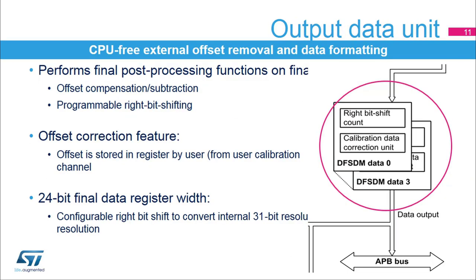The correct configuration must ensure the final data length fits into the 31-bit width, which is the resolution of the internal integrator. The width of the data coming from the digital filter must also be taken into account. The output data unit adjusts the final data before they are written to the final data register. An offset value that will be automatically subtracted from the data result for each channel can be defined in the offset register, determined using a calibration procedure programmed in user firmware. The maximum resolution of the final output data register is 24 bits, but the internal resolution can go up to 31 bits. A right-bit shift of the data, configurable from 0 to 31 bits, is available to provide the final data result with the required width without overflowing the 24-bit output register.